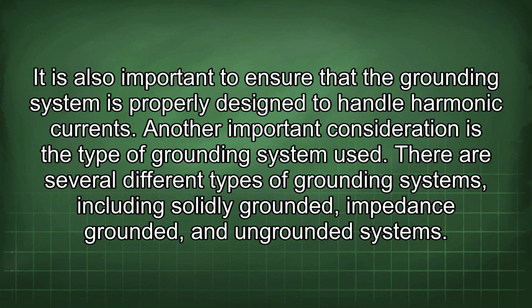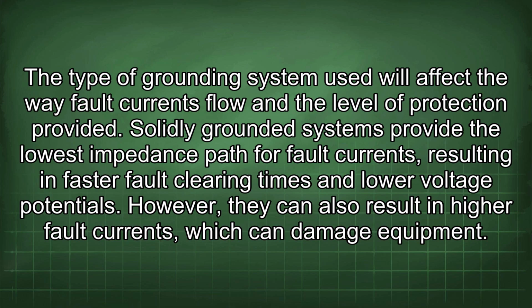Another important consideration is the type of grounding system used. There are several different types of grounding systems, including solidly grounded, impedance grounded, and ungrounded systems. The type of grounding system used will affect the way fault currents flow and the level of protection provided. Solidly grounded systems provide the lowest impedance path for fault currents, resulting in faster fault clearing times and lower voltage potentials. However, they can also result in higher fault currents, which can damage equipment.